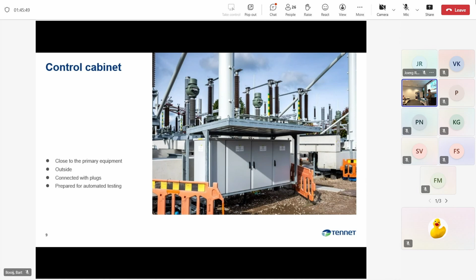It's connected with plugs and standardized cables to the primary equipment, which means it is prepared for automated testing. You can see a couple of my colleagues looking very interested at the plug compartment of the cabinet. Because those plugs are standardized as well, we can use an automated testing cabinet with automated scripting to test the whole cabinet before they go on site, with the configured software and 104 communication to the SCADA system.